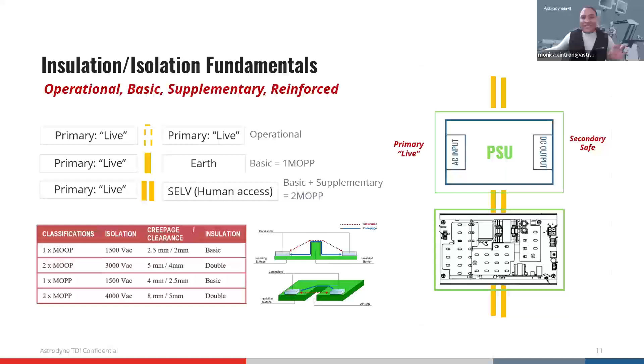But open versus enclosed also makes a big difference, because whenever you have an open system, a power system, a backup system, inverter, battery, whatever it is - the moment you open something, your hand should not accidentally make contact. So there are procedures intended to protect the operator. We definitely don't mean a consumer or patient opens something - that's unintended use. But the equipment classification brings about certain design considerations.